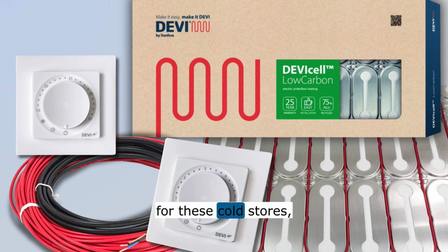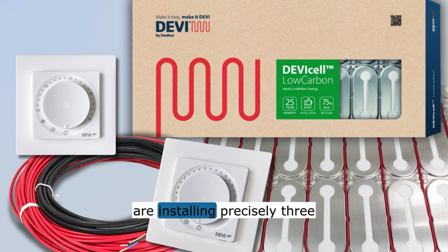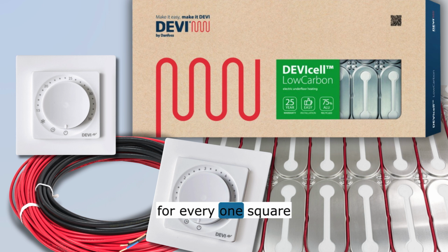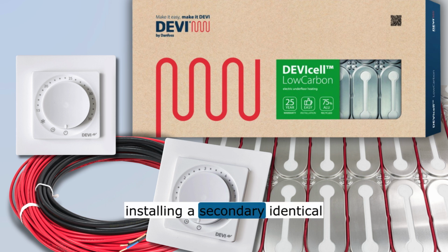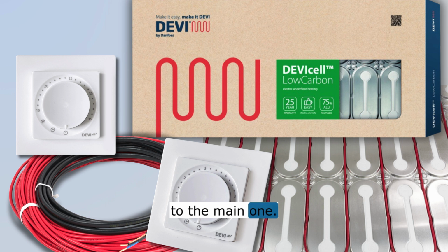The manual states that for these cold stores, the absolute maximum spacing is 50 centimeters, but they emphasize a preferred CC distance of 33 centimeters. Why 33 specifically? It provides a foolproof rule of thumb for contractors. A 33 centimeter CC distance means you are installing precisely 3 meters of heating cable for every 1 square meter of floor space. Ah, so it removes the complex algebra from the job site. Exactly. It makes purchasing materials incredibly straightforward. Also, because digging up a warehouse foundation is literally impossible, the manual mandates installing a secondary identical reserve system right next to the main one. Complete redundancy. Because you cannot afford a failure when the structural integrity of a whole building is on the line.